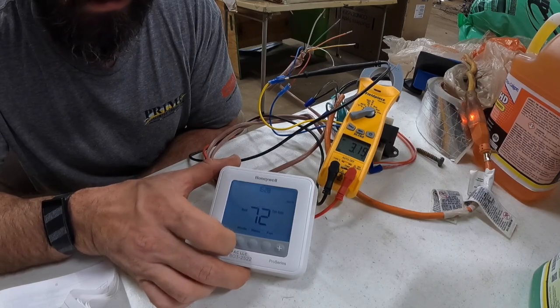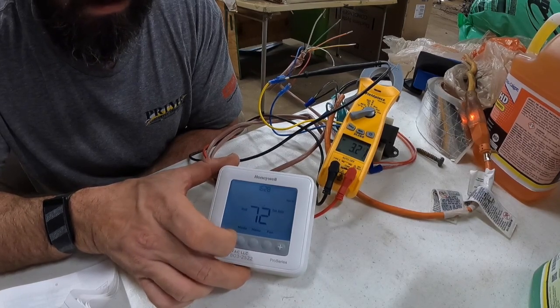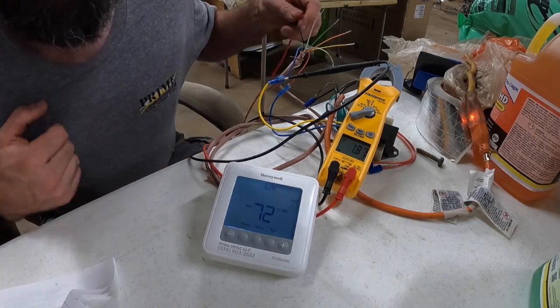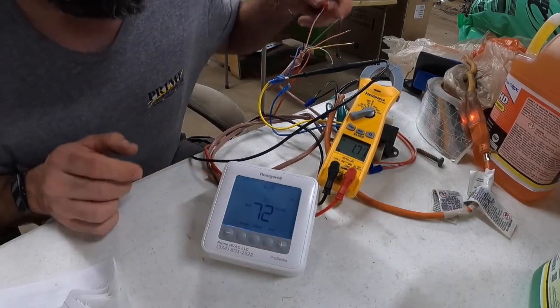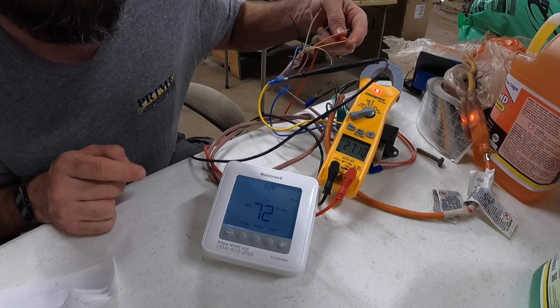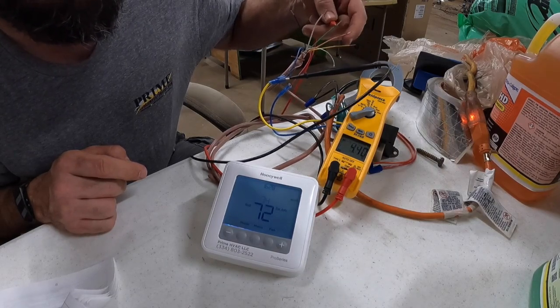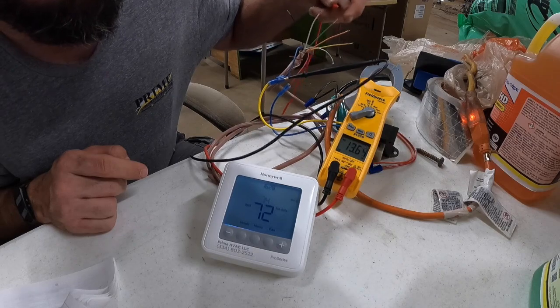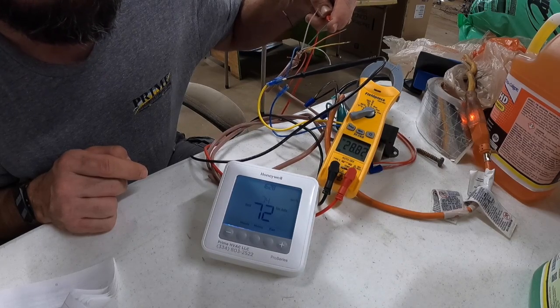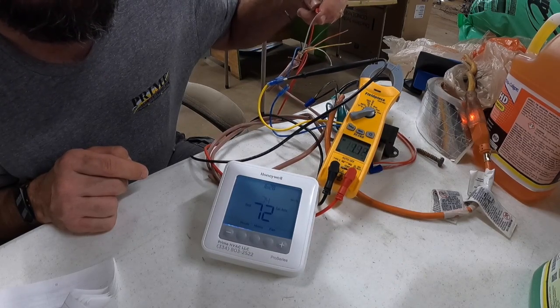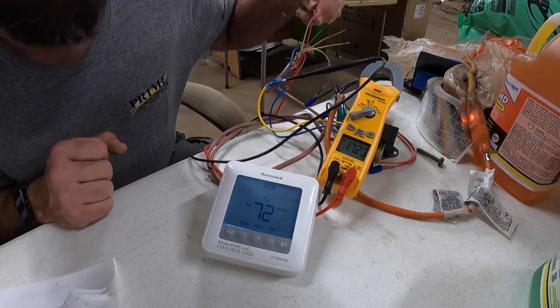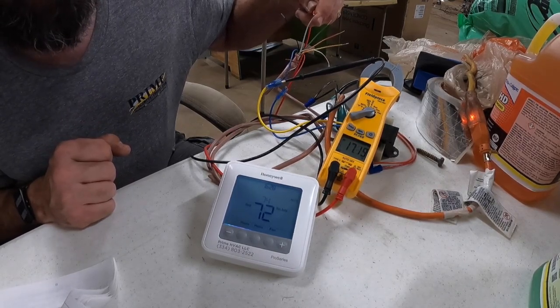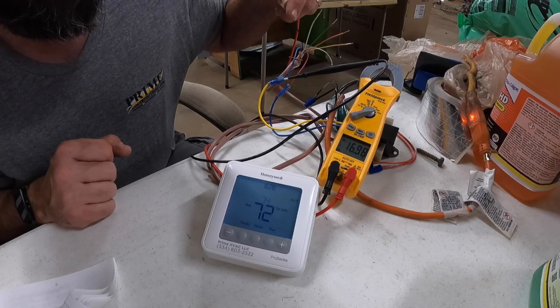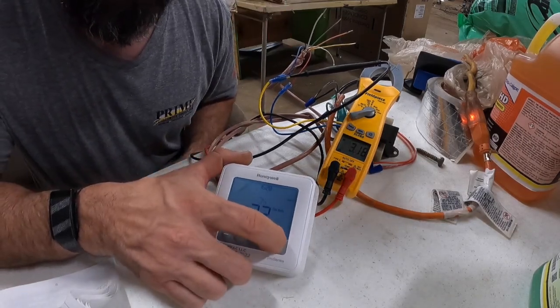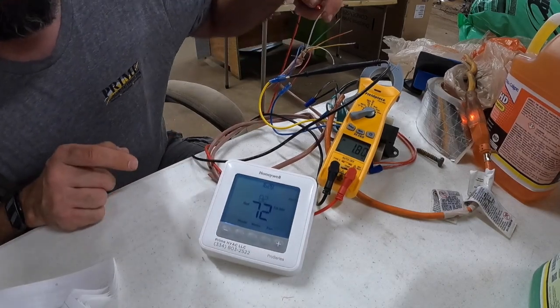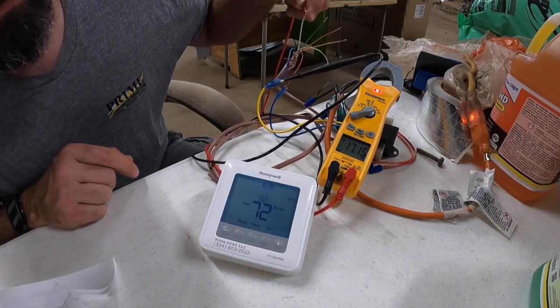Let's go back to heat and see if we can't get just the heat pump on. I think it's already doing that. Yep, 28 volts on Y. Nothing on O because we're calling for heat. G is energized. W is not energized yet. All right, so we're good there. Nothing on E. Let's go ahead and ramp this up to 82.